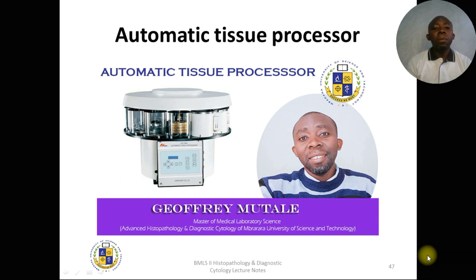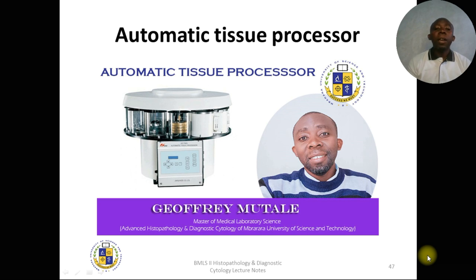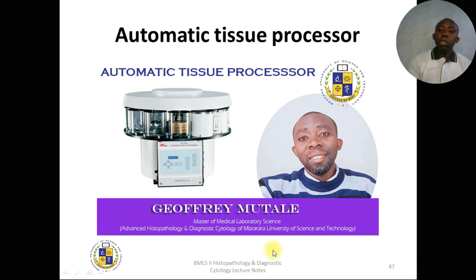The difference between the two main processor types is this: in one, the tissue itself moves from one beaker to another. In the other processor, the tissue remains in one position inside the processing chamber, and only the fluids are pumped in for an appropriate time, then removed and replaced with the next reagent.